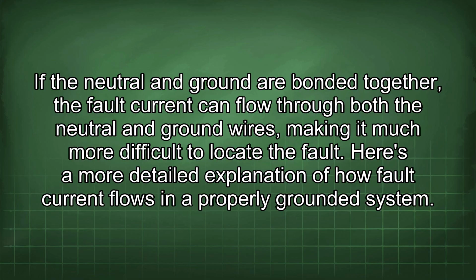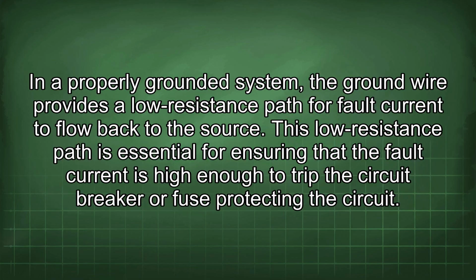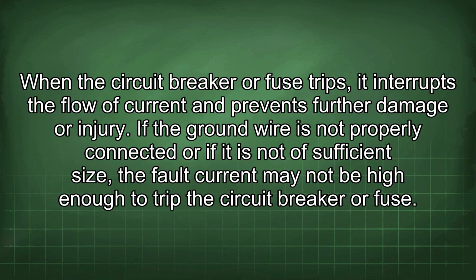Here's a more detailed explanation of how fault current flows in a properly grounded system. In a properly grounded system, the ground wire provides a low resistance path for fault current to flow back to the source. This low resistance path is essential for ensuring that the fault current is high enough to trip the circuit breaker or fuse protecting the circuit. When the circuit breaker or fuse trips, it interrupts the flow of current and prevents further damage or injury.